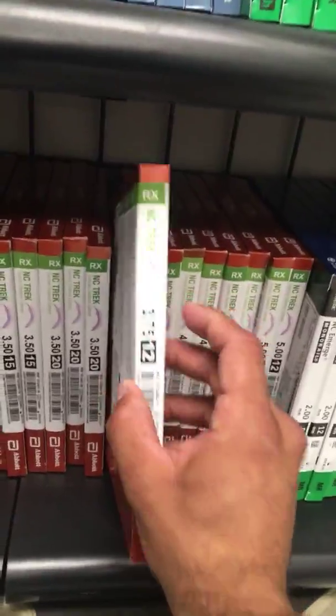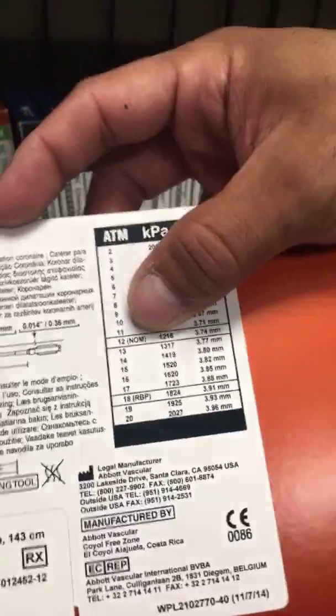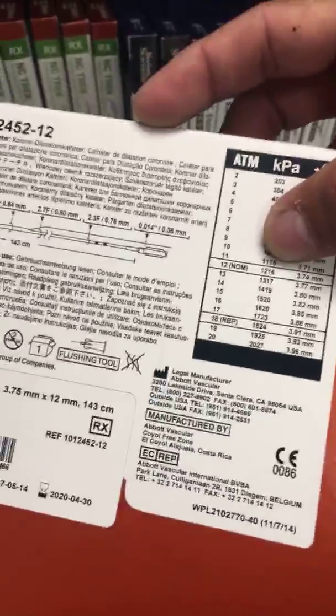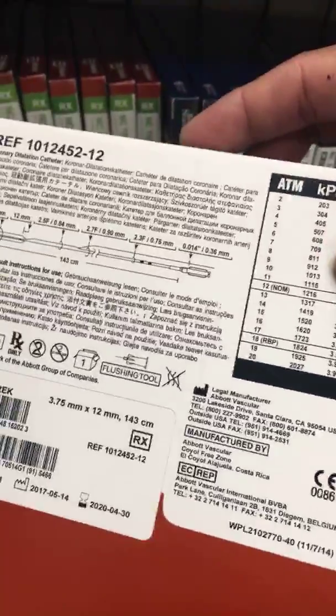Non-compliant balloons mean that there's no compliancy when you get to the nominal pressure. Nominal pressure is 12. You have to go to nominal pressure to get the non-compliance, meaning that the balloon won't flex. Once you get to 12, it's solid, stiff. You've got a 3.74, and you have to be able to get to nominal pressure to get that.